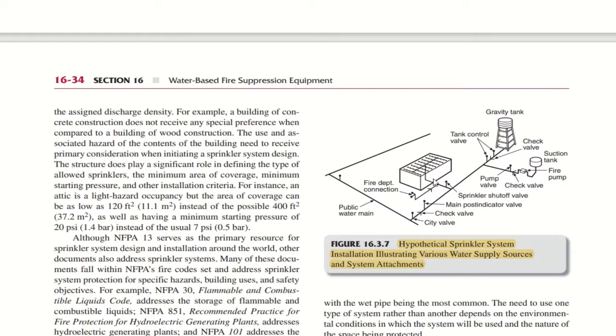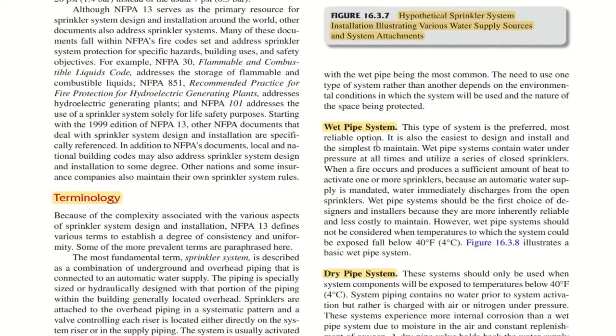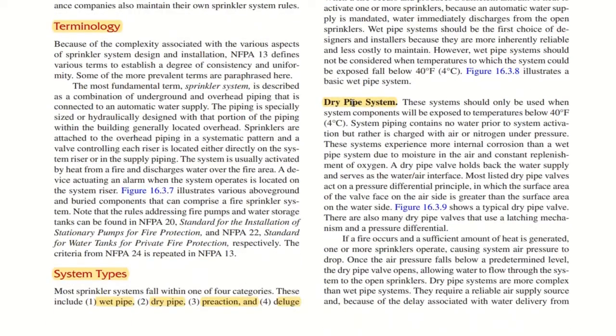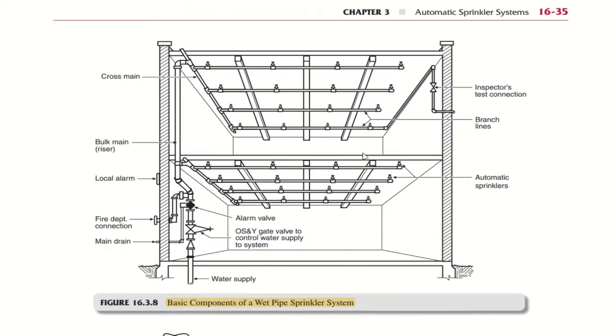So this will be connected to the building sprinkler systems. So here you have wet pipe systems, dry pipe systems. A dry pipe system should only be used when system components will be exposed to temperatures below 4 degrees centigrade or 40 degrees Fahrenheit. This is an important point, you need to make a note.